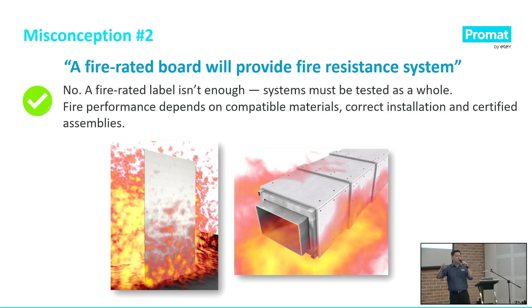A better explanation: timber can actually burn, it's a combustible material. If you ignite it, it will just burn. But with a combination of different components, it can become the so-called fire-rated board. So with your timber and everything combined, we put it into the test rig for a full-scale fire test, and we can get a 1 hour, 2 hour, or 4 hour fire rating. That means it needs to be built as a system to declare the fire rating, not just a single component itself.